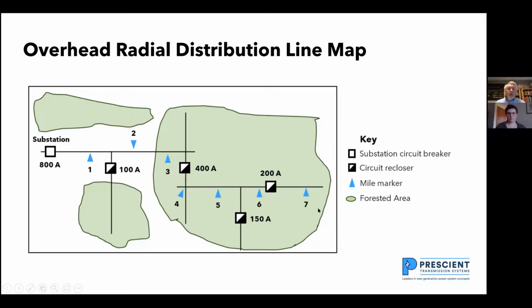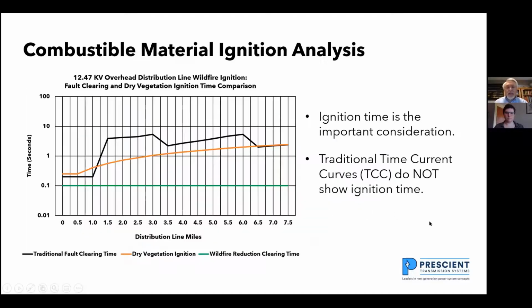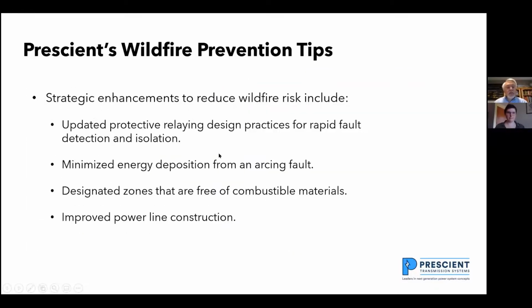When I'm in an extreme wildfire risk, I have to discard coordination as my main criteria. My main criteria is isolating faults before I ignite vegetation. So I'm going to update my protective relaying practices so that during the dry season, when temperatures are high and residual moisture is low, I'm going to clear faults as quickly as I can. This will minimize energy deposition from arcing faults. The energy deposition is a function of distance and time.